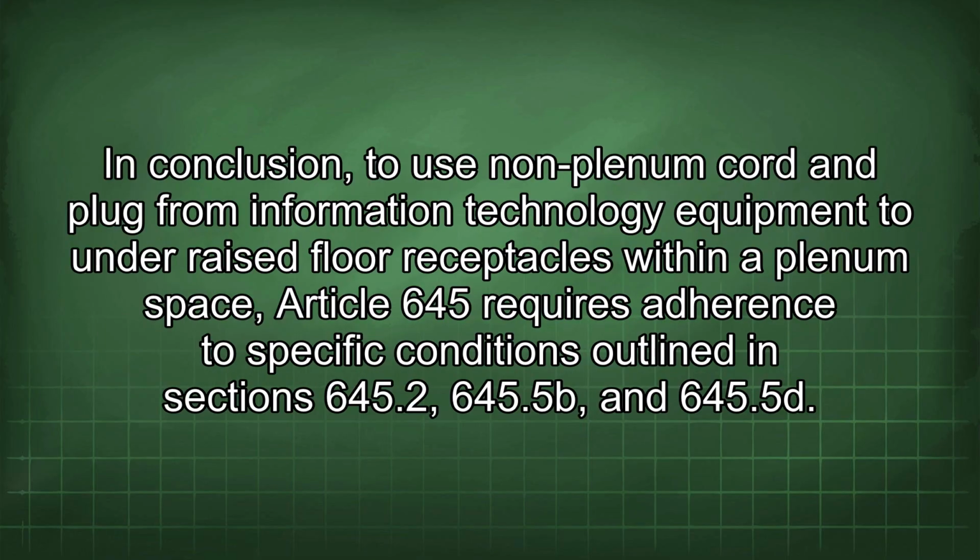In conclusion, to use non-plenum cord and plug from information technology equipment to under-raised floor receptacles within a plenum space, Article 645 requires adherence to specific conditions outlined in Sections 645.2, 645.5b, and 645.5d.